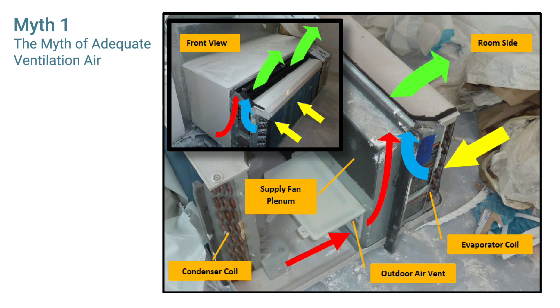This figure shows the vent door open: outdoor air passes through the outdoor coil (red arrows) and then through a washable filter at the vent. The ventilation air does not pass through the cooling coil before being mixed with return air (yellow). The return air goes through the evaporator coil where it is cooled (blue arrow), then mixes with the outside air (red arrow) and is discharged into the room (green arrow). The result is increased room humidity because the outdoor air has not been properly dehumidified.